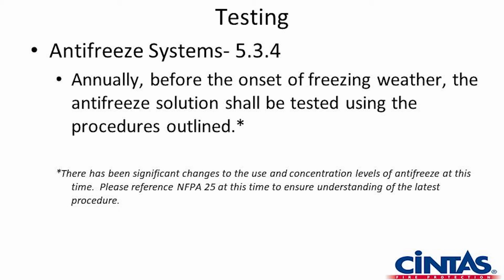We had an entire floor that was protected by a wet system, but we had a very small area outside. We could install an antifreeze system off of the sprinkler system, and we would add some valves, some backflow preventers and things like that to prevent the antifreeze from mixing with the sprinkler water and diluting the concentration.